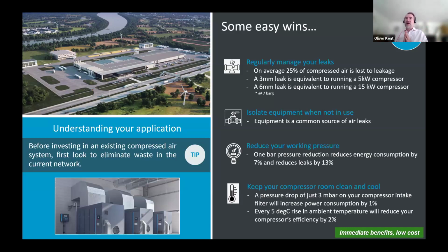And then finally, today's tip: when you're looking at your compressed air installation, before investing any serious money in updating or revamping your compressed air system, first do an audit on your compressed air system. Look to eliminate the leakage first, look to eliminate the waste first, do an audit on your working pressure, because you might find your compressed air system would actually function with a smaller compressor. So instead of a 110 kilowatt compressed air system, by the time you've fixed all the leaks and reduced its working pressure, you might actually have a 90 kilowatt compressed air system. And then you can invest in the capital equipment accordingly.